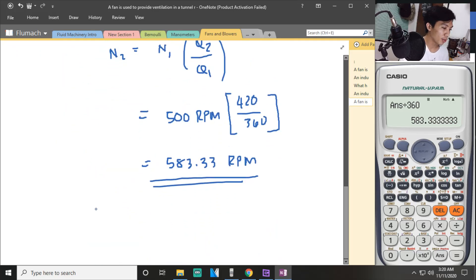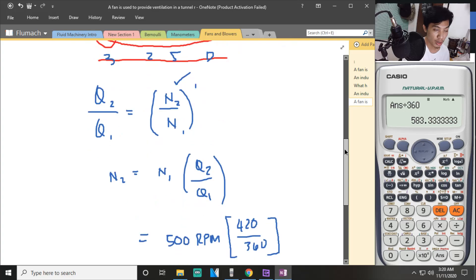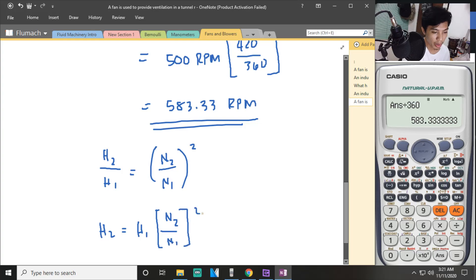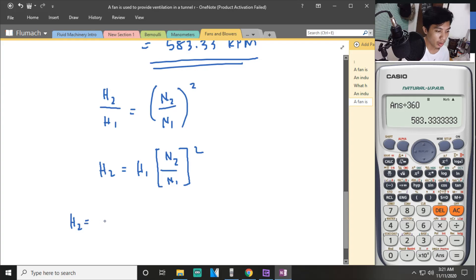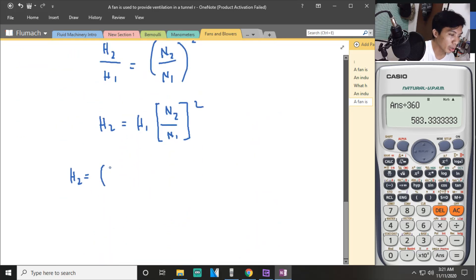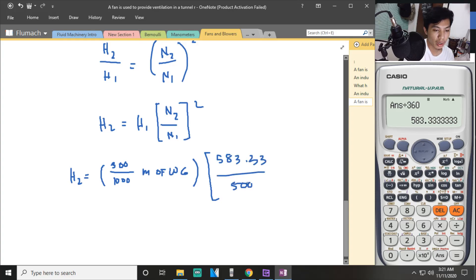Now that we have N2, we can solve for H2. Using the head affinity law: H2 over H1 equals (N2 over N1) squared. So H2 equals H1 multiplied by (N2 over N1) squared. H1 is 300 millimeter water gauge, which we convert to meters by dividing by 1000, giving 0.3 meters of water. Then we multiply by (583.33 over 500) squared.